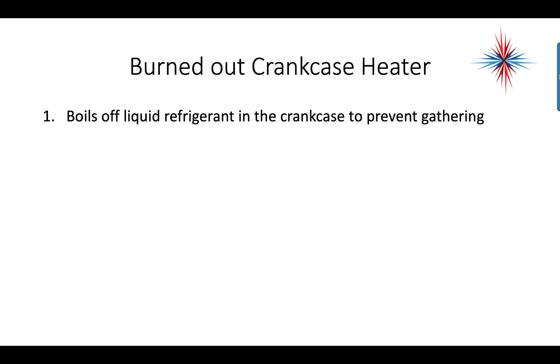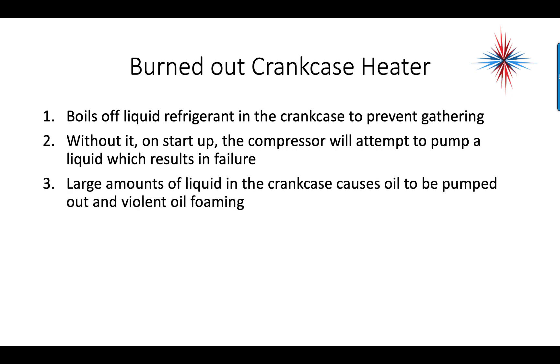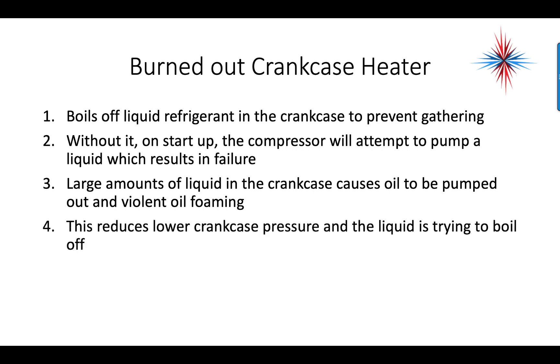A burned-out crankcase heater can also cause oil issues. The crankcase heater boils off liquid refrigerant in the crankcase to prevent it from gathering — remember, liquid refrigerant will always move to the lowest temperature area. Without it, on startup, the compressor will attempt to pump liquid, resulting in failure. Large amounts of liquid in the crankcase cause oil to be pumped out and violent oil foaming, which reduces crankcase pressure as the liquid tries to boil off.